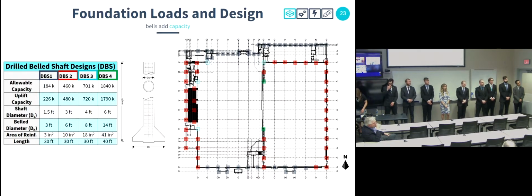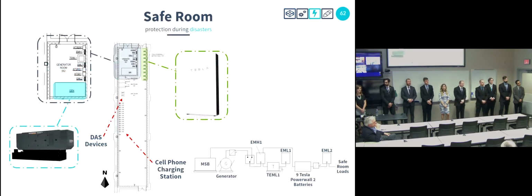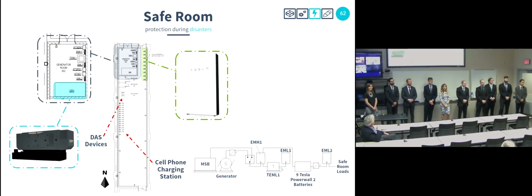I was also looking at clearances. You still need clearances around all sides of the unit—they have access panels and all that—typically 3 feet around the generators, so there's a little coordination there. You might be able to save some money by taking the enclosure out and just having an open generator with the muffler indoors. That's more common for a building like this.